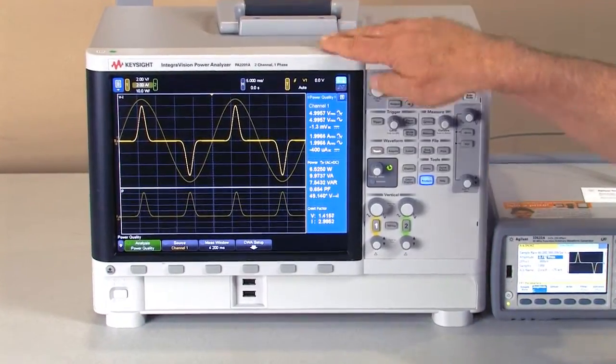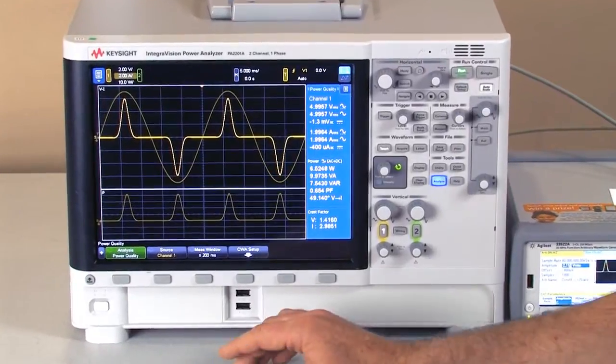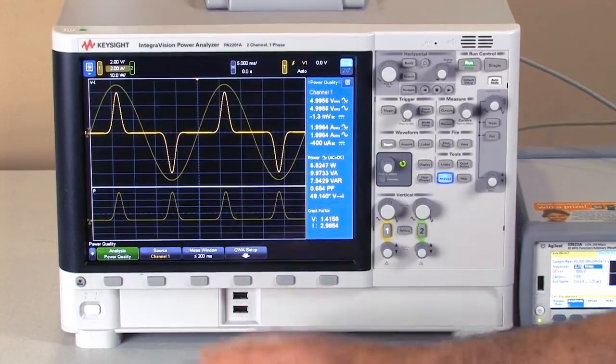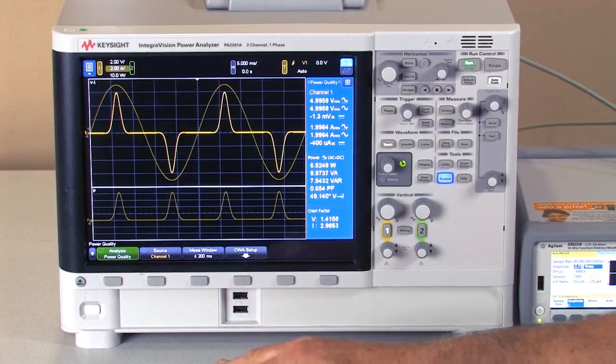Run those into channel 1 and you can see we have a normal sinusoid for the voltage channel and a very high crest factor for the current waveform.